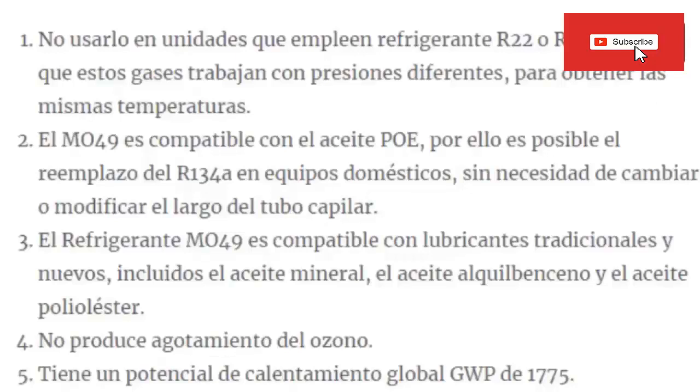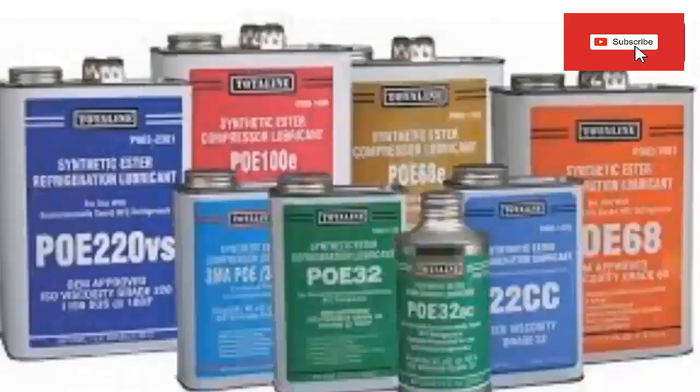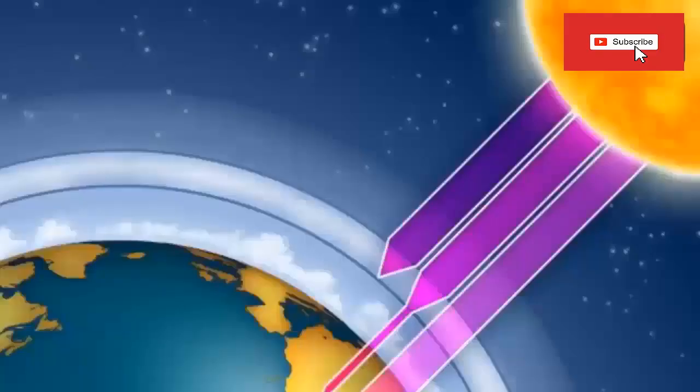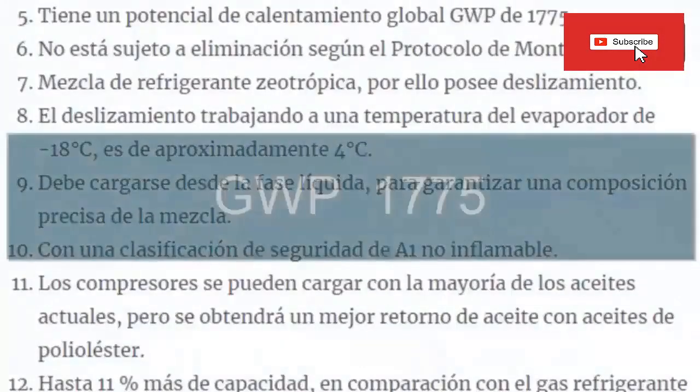3. MO49 refrigerant is compatible with traditional and new lubricants, including mineral oil, alkylbenzene oil, and polyolester oil. 4. It does not produce depletion of the ozone layer. 5. It has a global warming potential GWP of 1775.